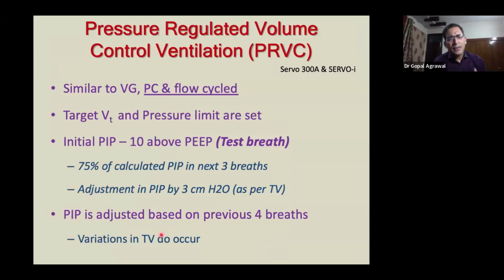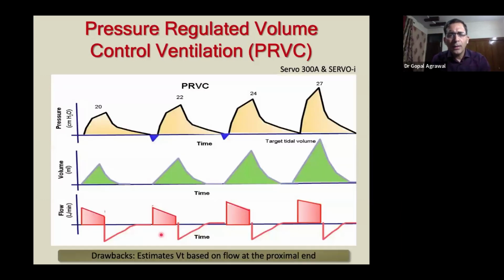The only difference is it adjusts its breaths over the next every 3 to 4 breaths. Volume guarantee is purely dependent on the previous one breath. Here, it's an average of the previous 4 breaths, and it will be an escalating and de-escalating control or variation. If we see it through the graph, the pressure will slowly keep on increasing, 20, 22, 24, 27, to get the tidal volume. It will not jump in the next breath. So it will be slowly escalating and de-escalating.